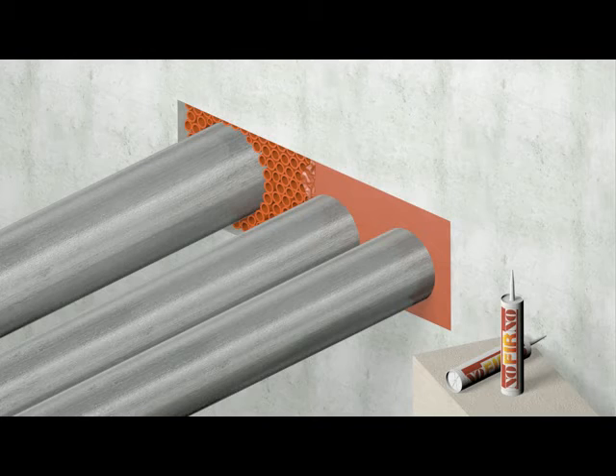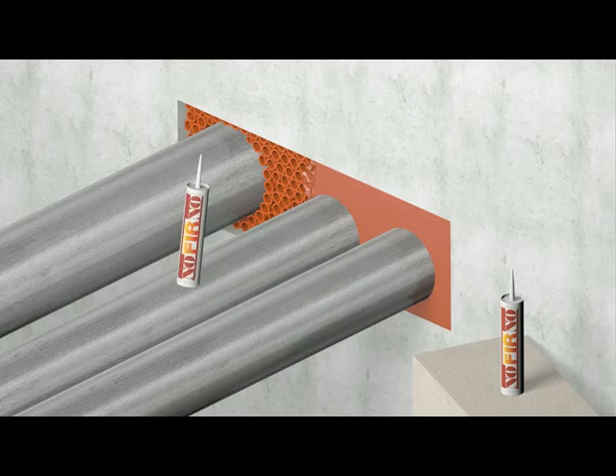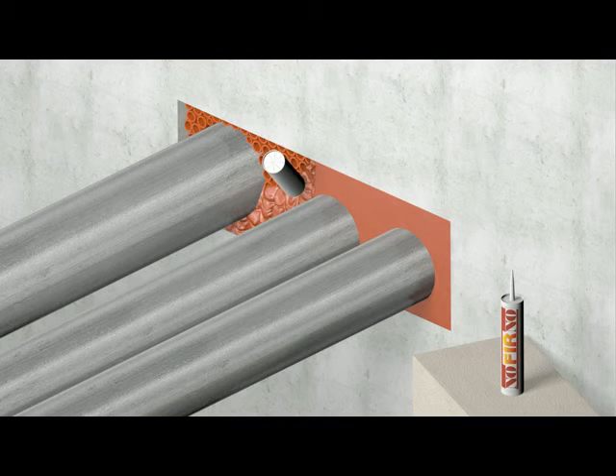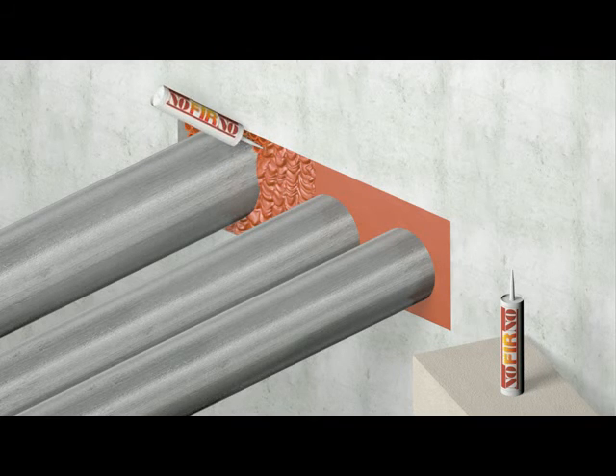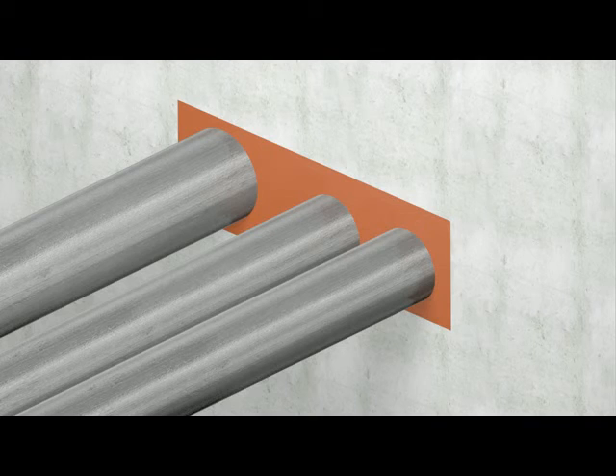Prevent soap water from being applied on the sealant surface, on which the next sealant will be applied. The adhesion between both layers will then be minimized. Then applying the sealant can be continued for the rest of the transit, smoothing and finishing in the same way as for the first part of the sealant layer.